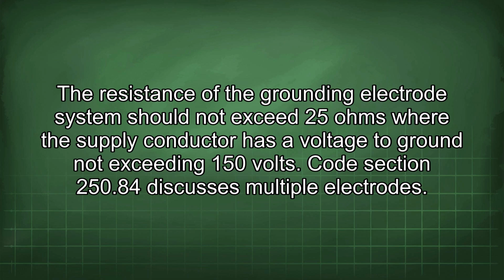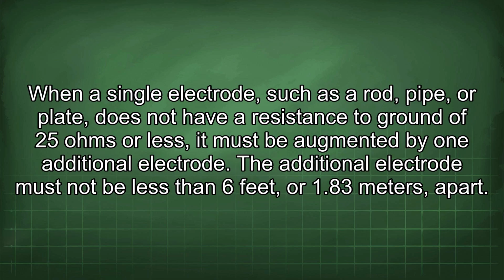Code section 250.84 discusses multiple electrodes. When a single electrode, such as a rod, pipe, or plate, does not have a resistance to ground of 25 ohms or less, it must be augmented by one additional electrode. The additional electrode must not be less than 6 feet or 1.83 meters apart.